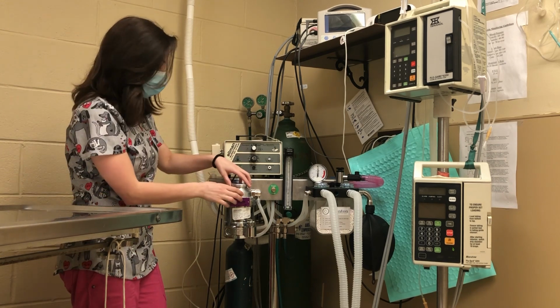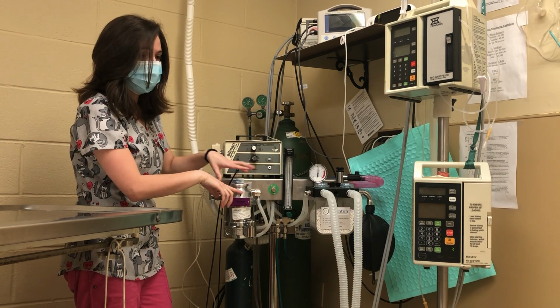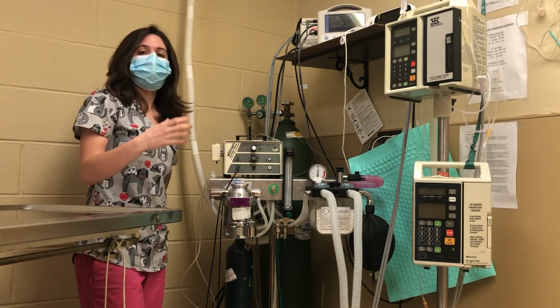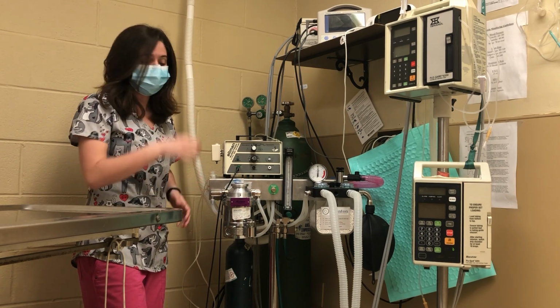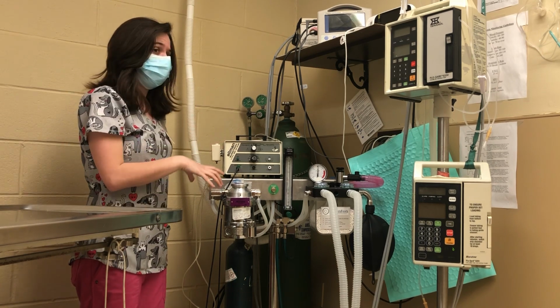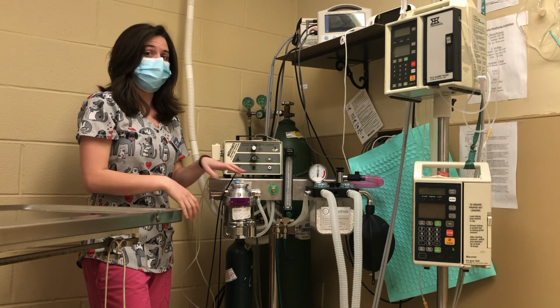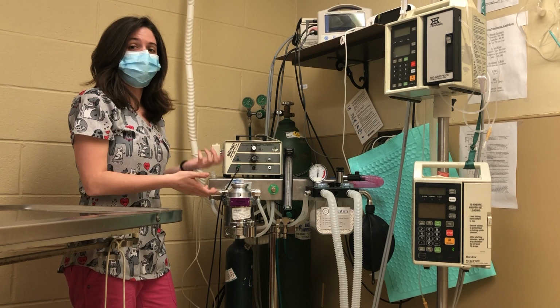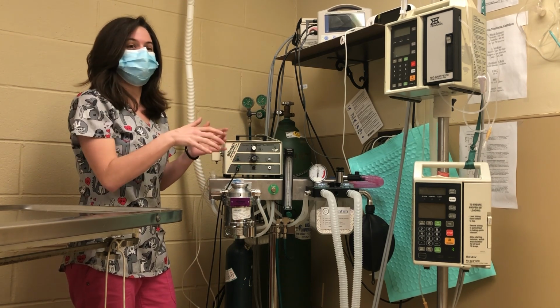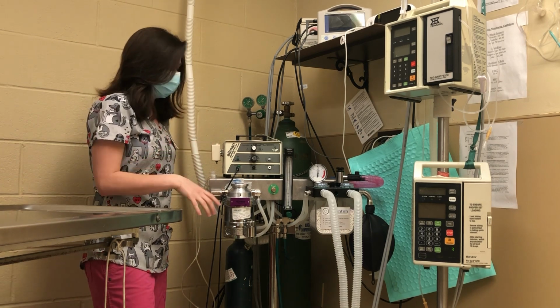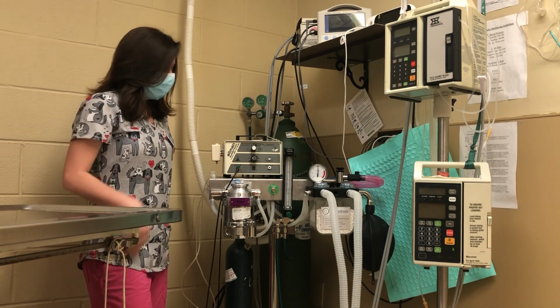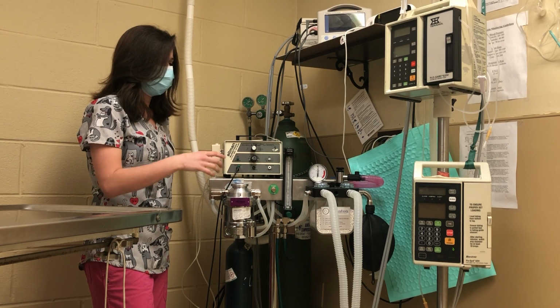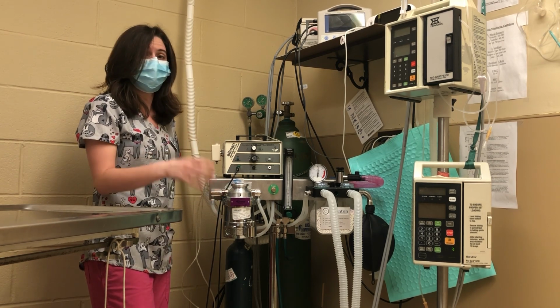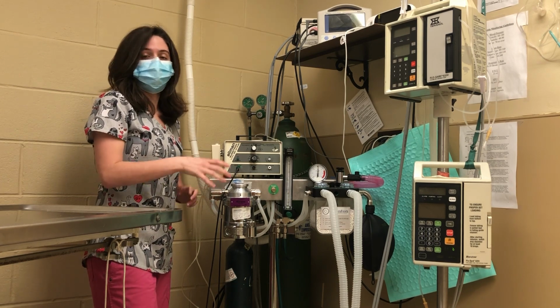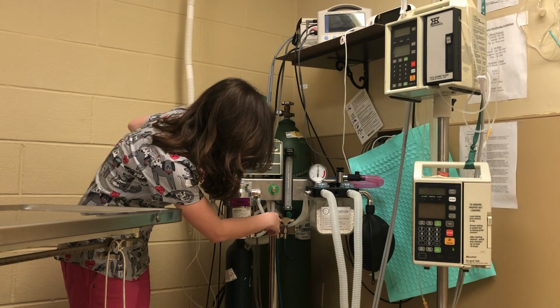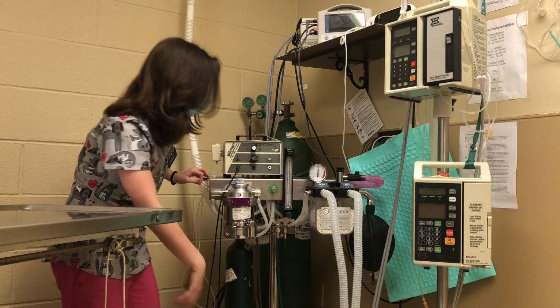So this is a precision vaporizer. We have a little knob here that lets us adjust the rate of our gas input. So the way this works is there is a liquid anesthetic in here. Most of the time it's isoflurane. And when our carrier gas goes in here, and we turn this on, our liquid anesthetic is vaporized into gas. So that is mixed with our carrier gas to form what's called fresh gas. And the isoflurane anesthetic can't actually leave this system until it's mixed in with our carrier gas at a controlled rate. So it will leave out one of these tubes here again into our breathing system, or breathing circuit rather.